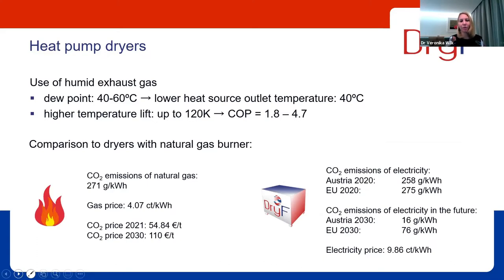And for a sound comparison, we will compare the heat pump to a natural gas burner that delivers the same amount of heat. I have put here Austrian values, and I will explain that a bit, because they might be different in other parts of the world. Starting with the CO2 emissions, in Austria we have rather green electricity. When you use 1 kWh of electricity, you emit 258 grams of CO2. And that's already less than the emissions from natural gas, with an average value of 271. And the European average is quite close to the emission of natural gas.